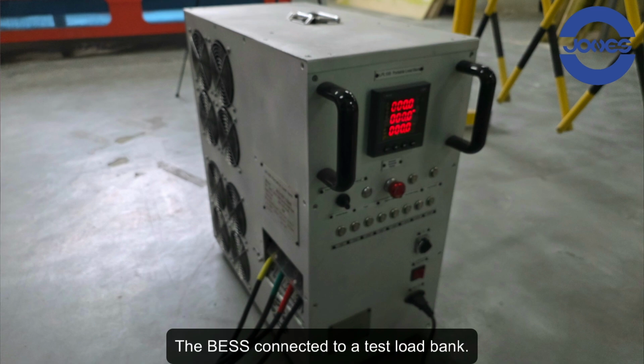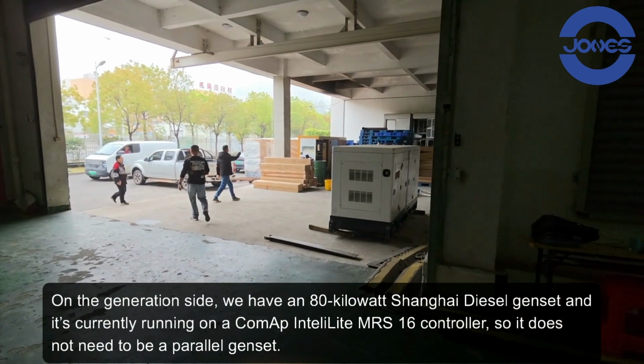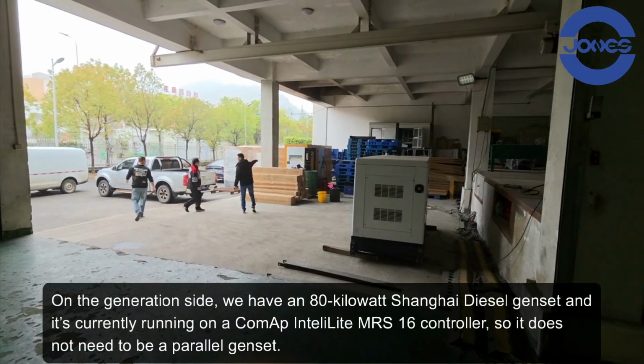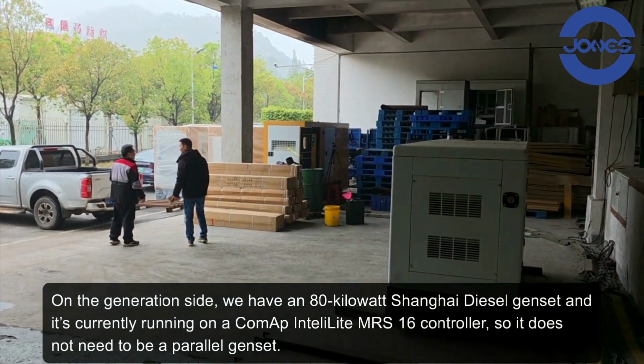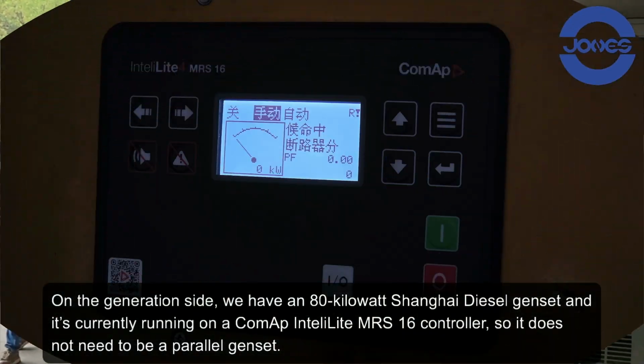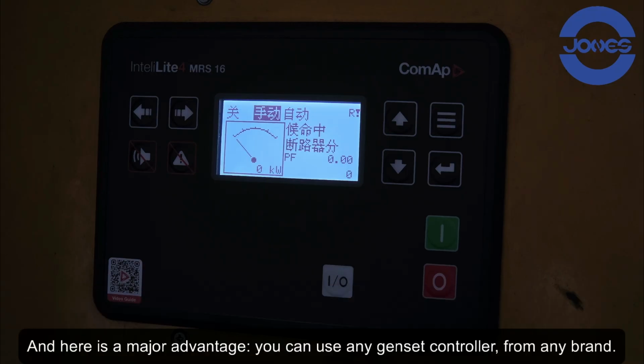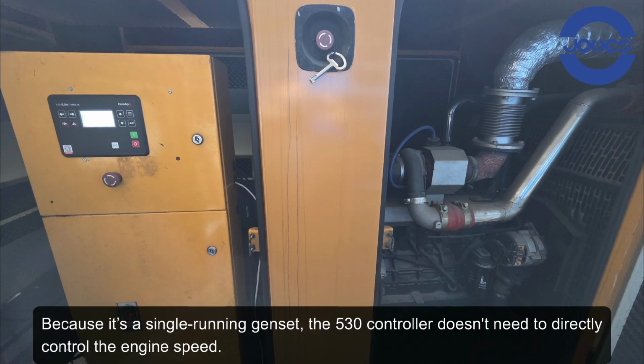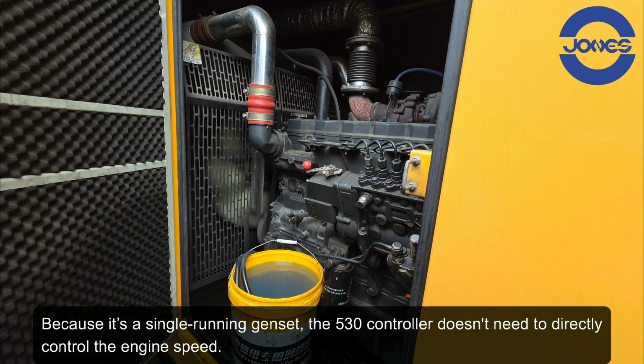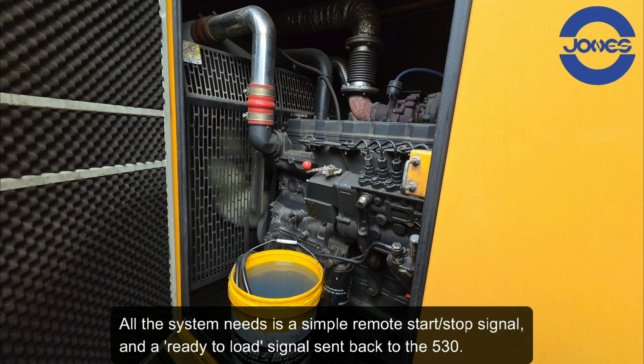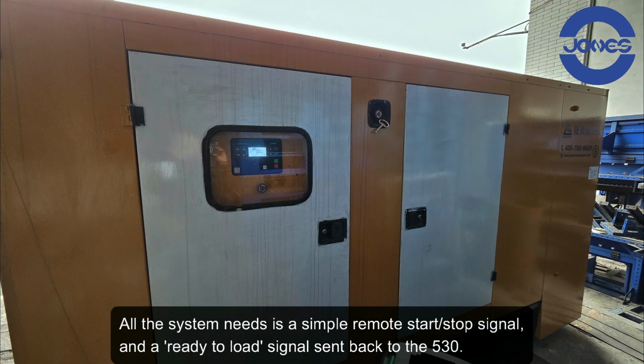The BESS is connected to a test load bank. On the generation side, we have an 80 kilowatt Shanghai diesel genset, and it's currently running on ComAp's InteliLite MRS16 controller, so it does not need to be a parallel genset. And here is the major advantage: you can use any genset controller from any brand. Because it's a single running genset, the 530 controller doesn't need to directly control the engine speed. All the system needs is a simple remote start-stop signal and a ready-to-load signal sent back to the 530.